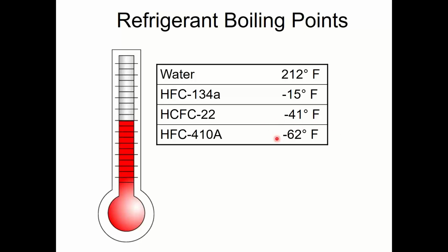And if you didn't know it, coming down the pipeline here, R22 is actually obsolete. You cannot buy any equipment manufactured with R22 since 2010, and they stopped making replacement refrigerant in 2020. So now you can only get refurbished refrigerant. R410A is on the same chopping block, by the way. Different manufacturers have different solutions they're working on. A lot of them are going to use R454B, but that's a whole other discussion for a whole other day, because we're still several years away from that discussion, right?